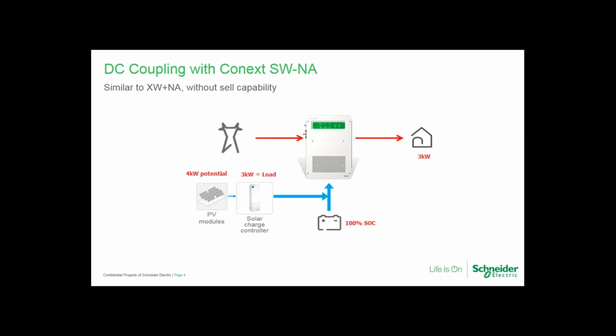Grid connected systems that use Conext SW will reduce the draw from the grid commensurate with solar production once the batteries are full. The Conext SW has no sell capability. So once the batteries are full, the solar power cannot be harvested under conditions where PV energy exceeds load demand. For example, the charge controller has 4 kW of available solar, but the load is only 3 kW and the batteries are full. So this means the PV output will only be 3 kW, because that extra 1 kW has nowhere to flow.